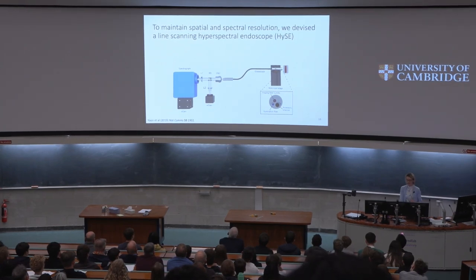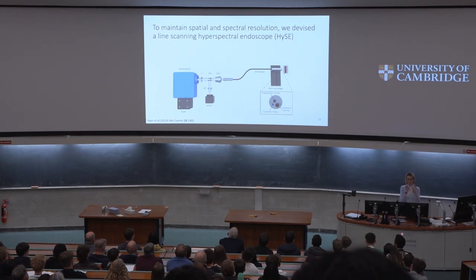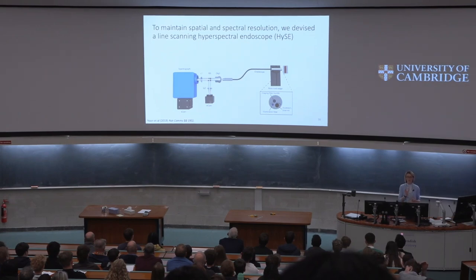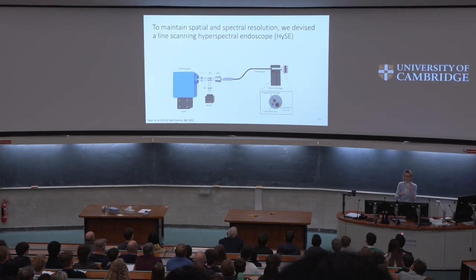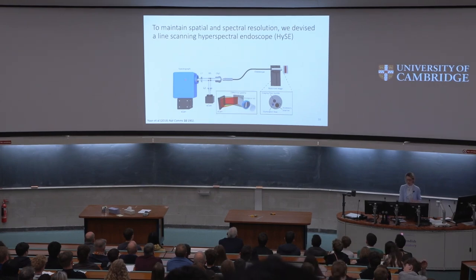We have our 10,000 fibers running through the endoscope, and the picture of those 10,000 fibers gets imaged onto an objective lens. That image then gets split in two directions. We send part of the light to a standard white light camera, so we are always watching those 10,000 fibers as they move around, monitoring the field of view. The rest of the light gets sent through to a 2D spectrometer.